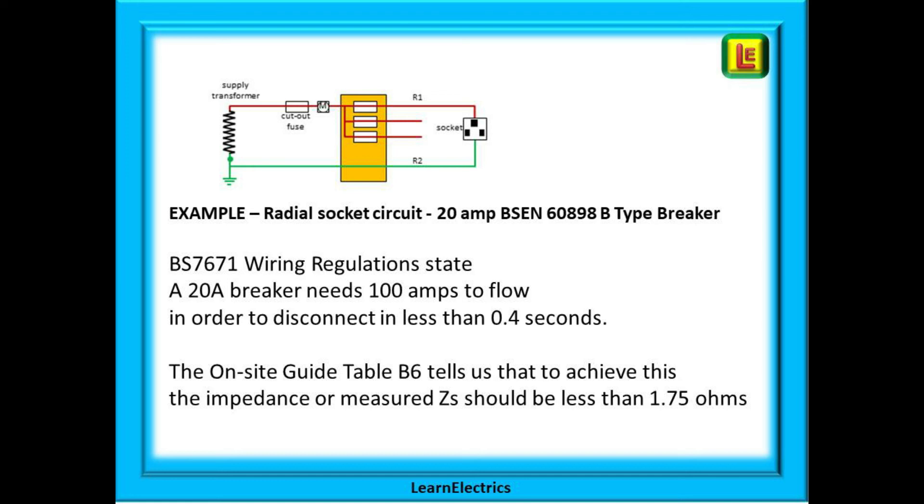These tables have also been adjusted for voltage and temperature variations. All the electrician needs to do is measure the ZS of the circuit and compare the reading on the test meter to the values in the standard tables. If the ZS reading that has been measured is 1.75 ohms or less, then even taking into account voltage and temperature fluctuations, at least 100 amps of fault current will flow and the MCB will trip in 0.4 seconds or less. This will ensure that the circuit complies with the requirements of the electrical regulations for safety.